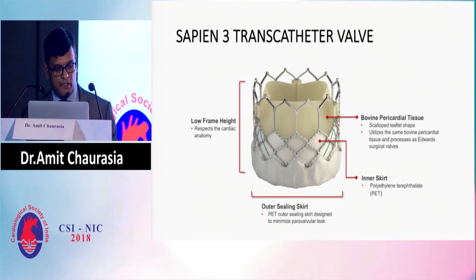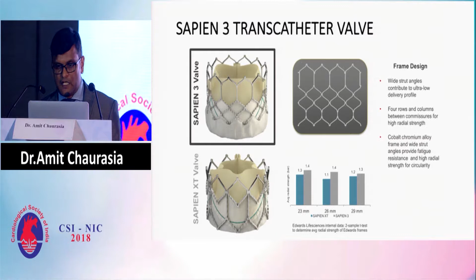The valve struts are made out of cobalt chromium, and it has the widest struts on the top, which helps in decreasing the profile of the valve. In between there are 4 struts which increase the radial strength, and the lower portion again becomes wide enough. This is to increase fatigue resistance at the annular level, as well as to improve the radial strength so that circularity is maintained.